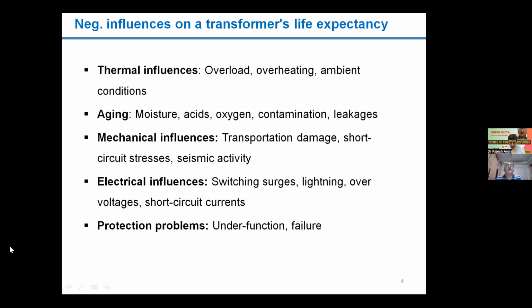So if we look into what the different negative influences are, what the different factors are which may affect the life of the transformer, we may list out these factors like thermal influences due to overloading, overheating, then ambient operating conditions, age-related issues, meaning moisture may ingress inside the transformer through different joints, tank openings, etc. Then acid formation, oxidation. Oxidation is again, if some leakage takes place, then that oxidation may occur at different terminations, maybe somewhere the bushing termination, then winding connections are there like that.